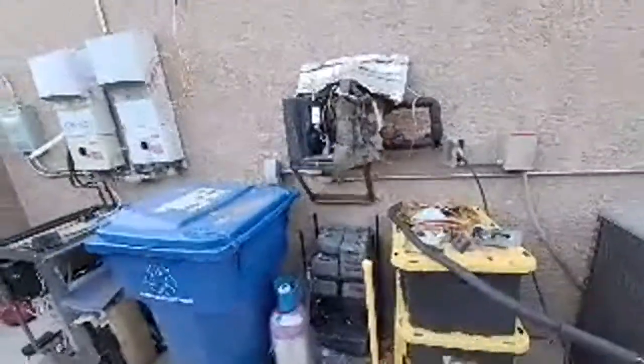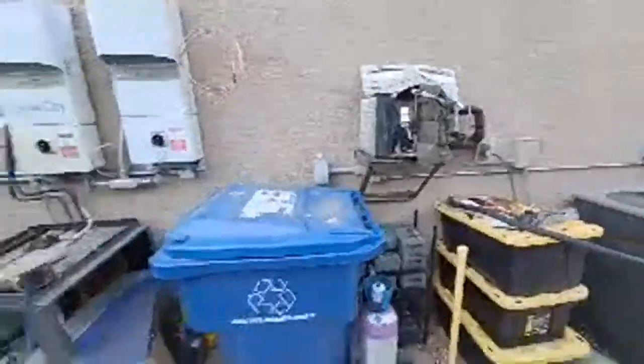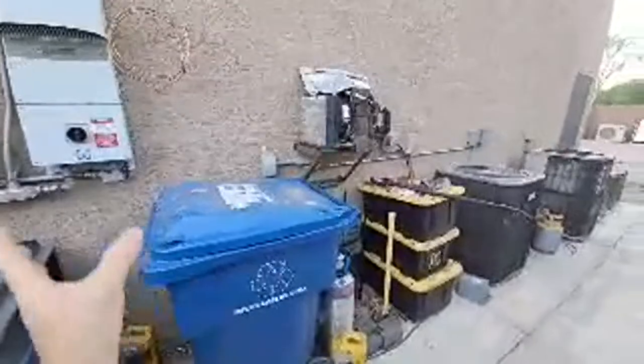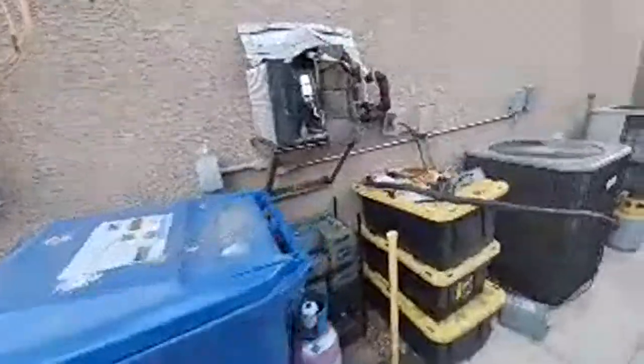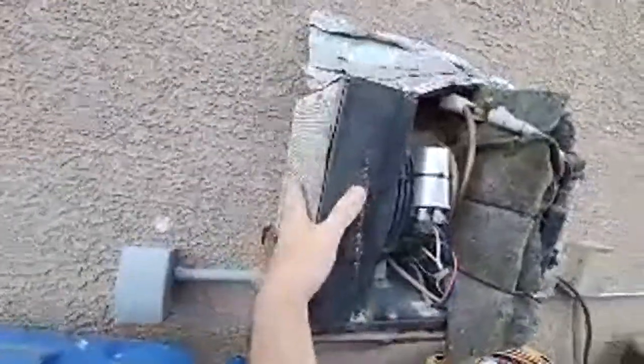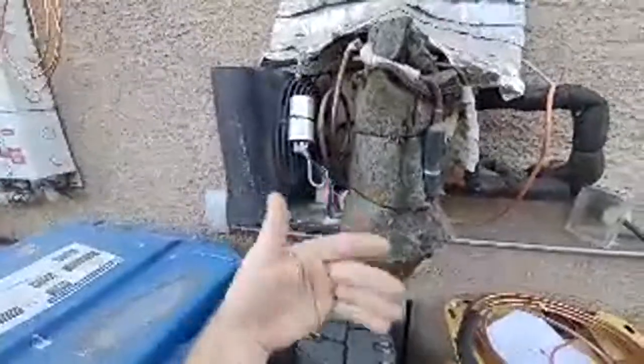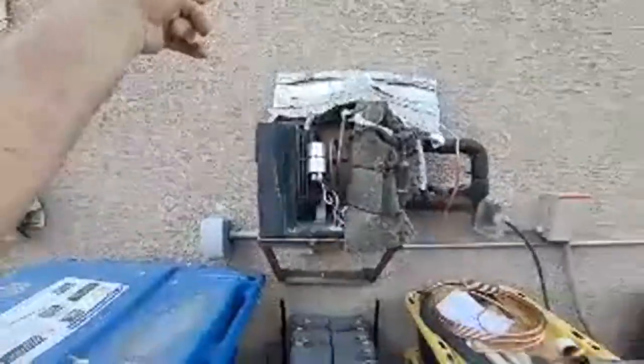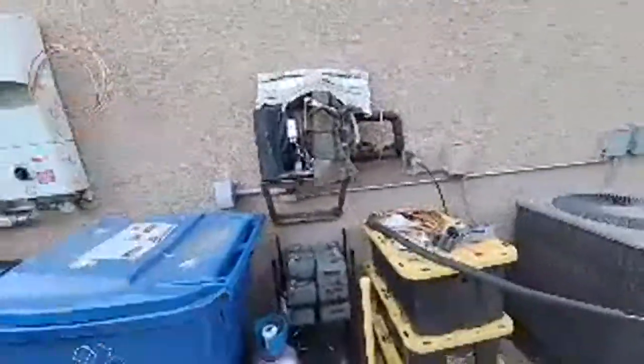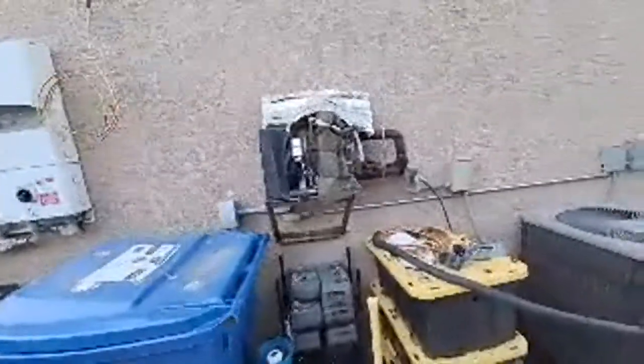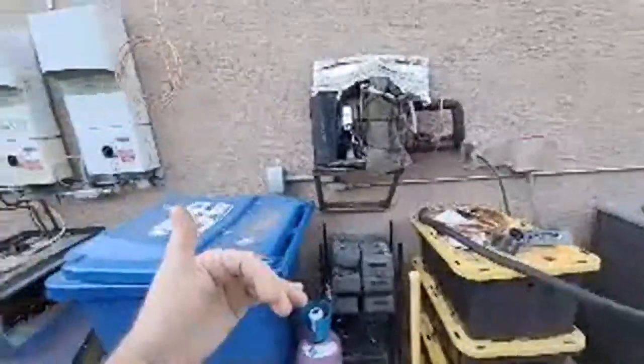But I have this idea that I can do a bunch of crazy stuff and make one unit cool my room and heat the water, which is going to have me do some weird things because in the winter, you know, and like right now this is the evaporator. I turned this condenser into an evaporator, but it just takes heat out of the outside air and blows cold air out here, doing me no good. I could be cooling the space right now with the same electricity that's heating the water. That's fine and dandy for the summer, but in the winter, you don't want it to cool inside. It freezes you out. So I'd have to make a dual evaporator unit out of the next one if I do that. So it'd be an outdoor evaporator, an indoor evaporator for the summer, and then switch to the outdoor one.